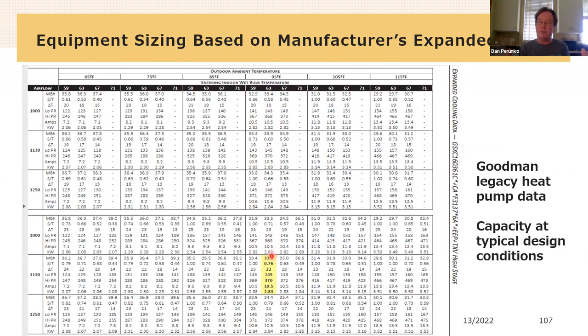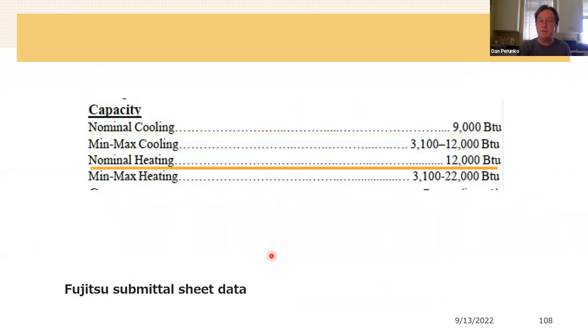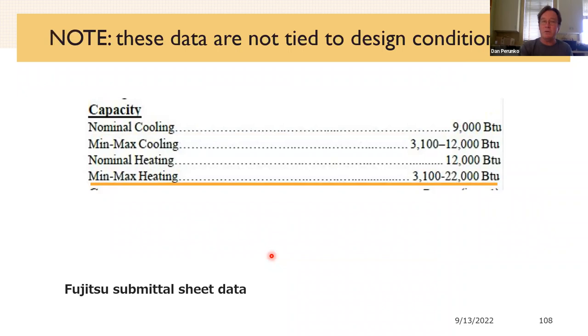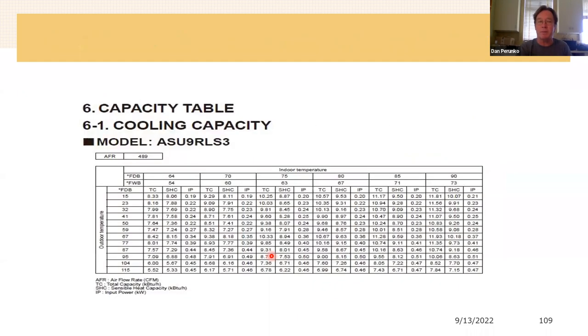And again, we could spend all day talking about how to do this. This is the thing you need to learn. There are classes about Manual J and equipment selection, and that's where you go to figure out how to do this. But just know that if you do a load calc and it says that your system has a 2-ton load, you can't necessarily just go buy a 2-ton heat pump. It's a little more complicated than that. This is another example of expanded data. This just happens to be from a different manufacturer.